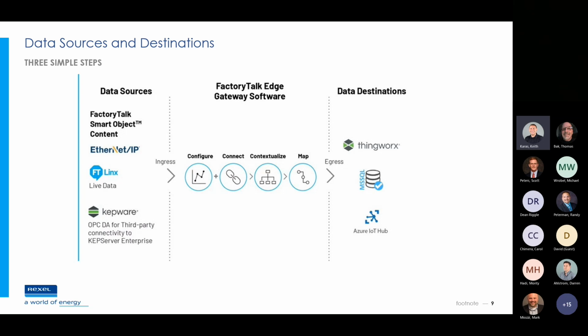And where this is helpful is if, as I mentioned before, you have the legacy content out there, and let's say you have a SLC 5/05 and you want to enable some Ethernet connection to it, you can utilize OPC DA. There's also ways with gateways that talk to OPC with different things. So we can take some of those legacy pieces of equipment if we're not ready to make that transition to new controllers that have that data on demand. Kepware and OPC is a good driver for that, especially if you have third-party equipment out there as well, along with your Rockwell content.